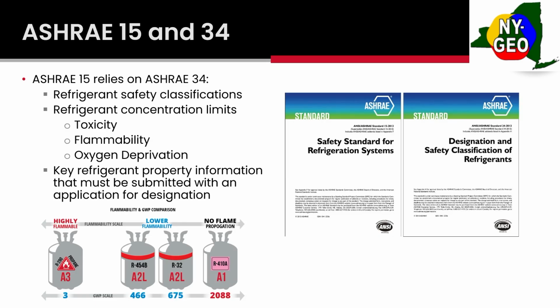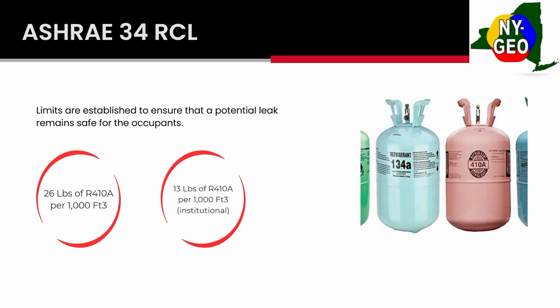Now when you're designing with ASHRAE 34, you can't do it without ASHRAE 15. ASHRAE 15 is going to be your design guide, and then ASHRAE 34 is going to give you the formulas you need, the LFL, the lower flammability limit, and all your key information on the refrigerant that you're going to use for ASHRAE 15 to plug into your formulas. So ASHRAE 34, what we use for 410A is the refrigerant concentration limit when we're designing around ASHRAE 15.